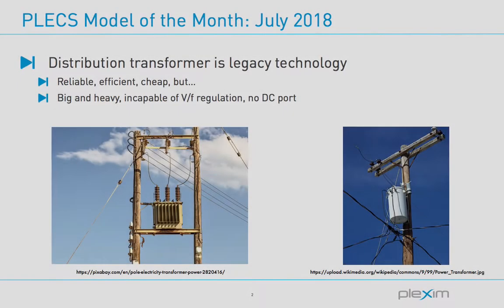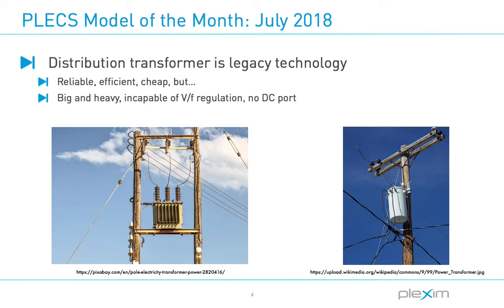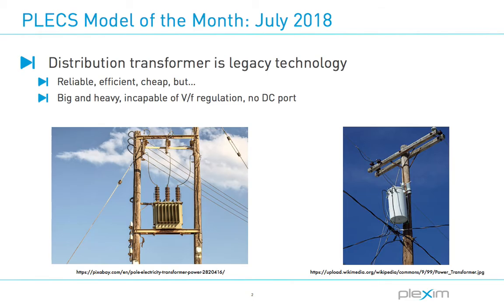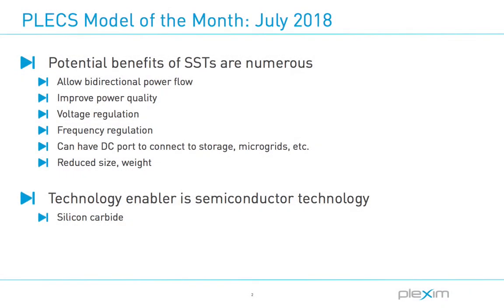I will first introduce what a solid-state transformer is. Historically, traditional transformers have been deployed for voltage transformation in power distribution networks. As these typically operate at line frequency, the transformers are very bulky and heavy, and offer no additional benefits. They are also passive systems that only allow unidirectional power flow. SSTs have been discussed for a number of years as a way to both solve this size and weight issue, as well as to add new functionalities.